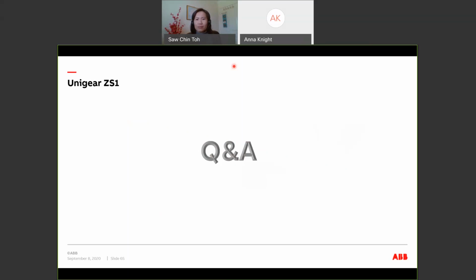Okay, thank you. Another question here is: can you remote rack your circuit breaker and contactor? And if yes, what is the mechanical endurance? The circuit breakers and the contactors are all designed with the option of remote racking, and this has been tested rigorously. It is tested to at least 10,000 operations. We have tested the switchgear racking in and out, the motor operations together with the truck inside the panels, for up to 10,000 operations.